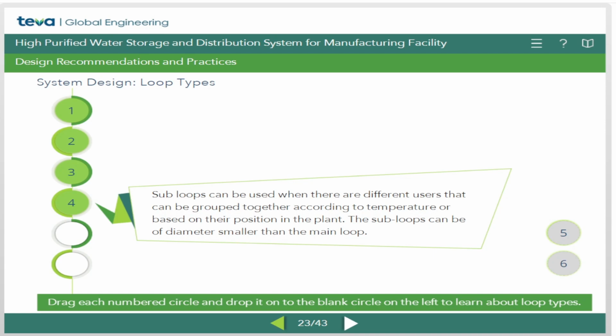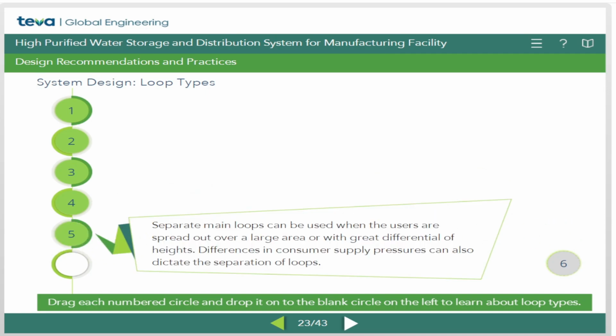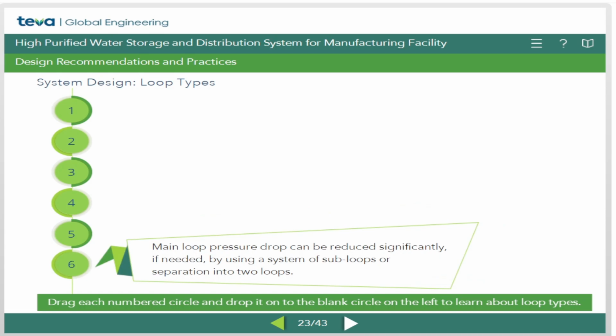The subloops can be of diameter smaller than the main loop. Separate main loops can be used when the users are spread out over a large area or with great differential of heights. Differences in consumer supply pressures can also dictate the separation of loops. Main loop pressure drop can be reduced significantly if needed by using a system of subloops or separation into two loops.